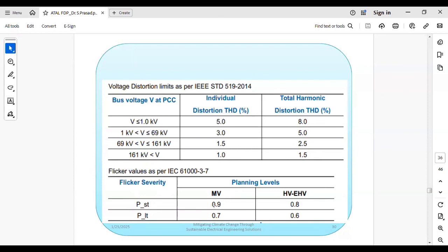For MV system, it is 0.9, 0.7. You have to find it out. In software, this facility will be provided to run the flicker analysis, and it has to be within 0.9 or 0.7, depending on what would be long term and short term flicker severity. You need to find it out. According to the standard, they will verify whether we are fulfilling all the terms and conditions.